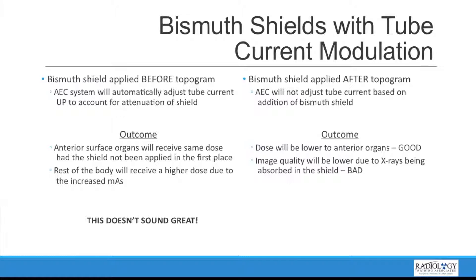What happens if we apply a bismuth shield after the topogram? The AEC will not be adjusted based on what is seen in the topogram for most scanners — some scanners can change this on the fly, but let's assume it isn't changed. The outcome is that doses will be lower to the anterior organs, which is what we're trying to achieve. However, the image quality is going to be degraded because there are fewer x-rays contributing to image formation since they're being absorbed in the shield. So we end up with a decrease in image quality, which means this option doesn't sound that great either.